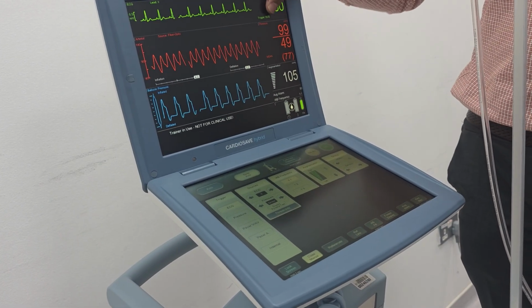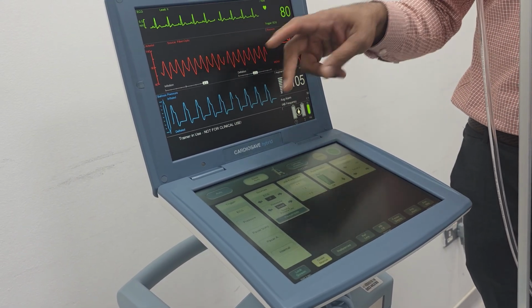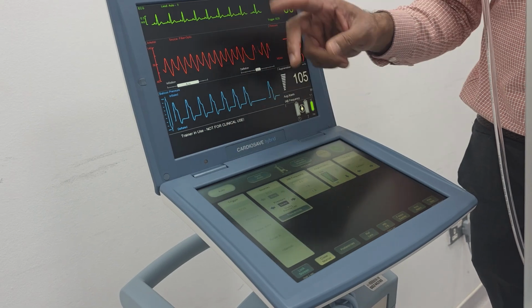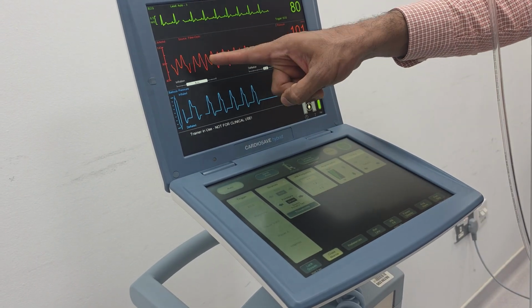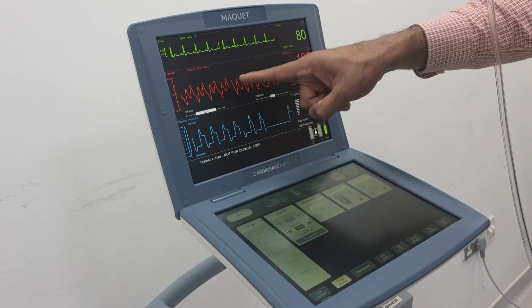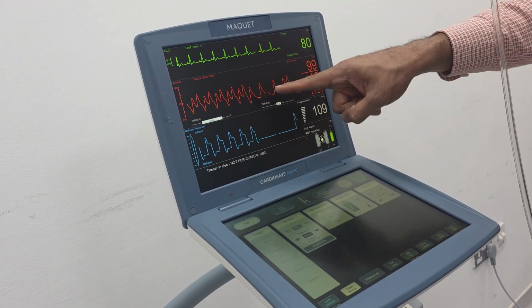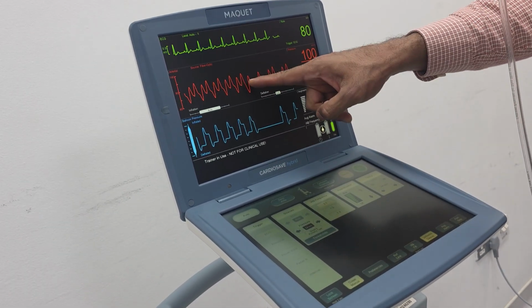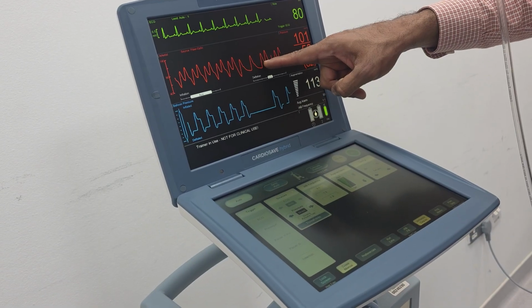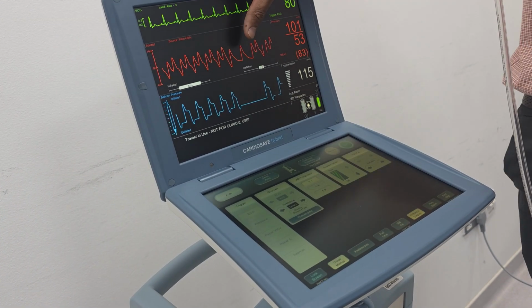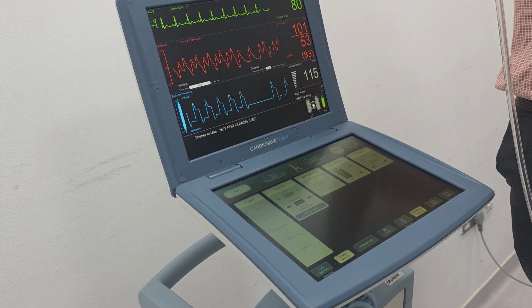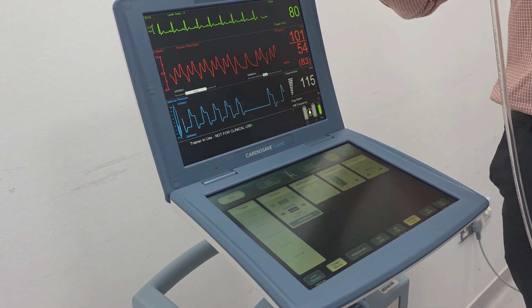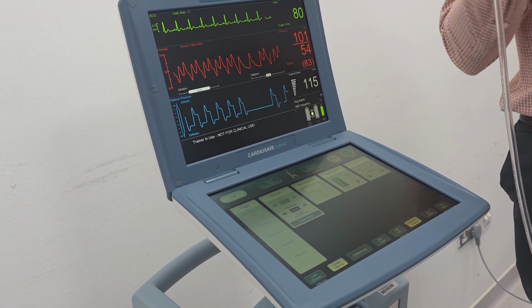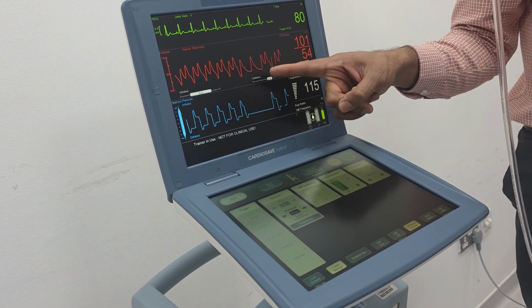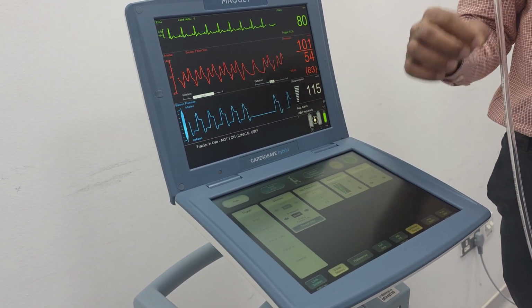It is triggering based on the R wave now. Okay. I put it back to auto mode. Okay. Came back to auto. You can see the dicrotic notch still. Now it missed 2 beats. Still you can see, every 15 seconds in the initial conditions it will miss 2 beats. Even if it is triggering based on the ECG, it will keep on checking the R wave and the dicrotic notch in the pressure waveform to see the timing. It is called auto updation.